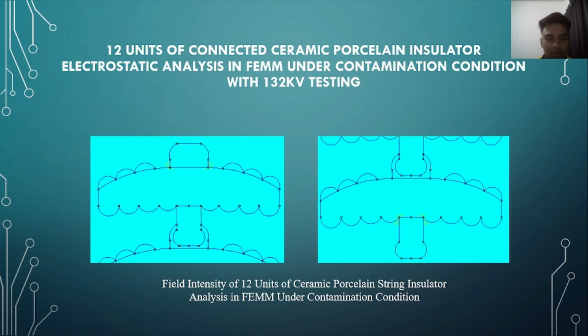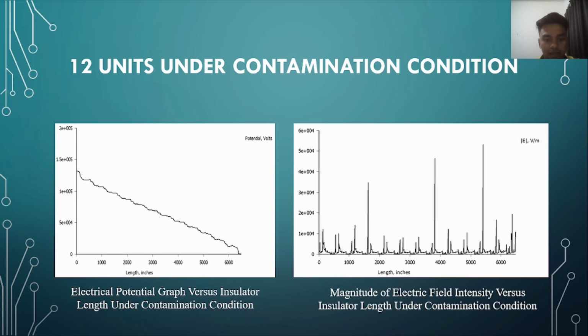Next we go to the first unit of the ceramic insulator electrostatic analysis in FEMM under contamination condition with 132 kV per phase. Here the field intensity is small, with a little field intensity above and under the insulator. This is the result for the contamination condition. In FEMM, the voltage is centered on the bottom of the insulator design, the voltage parameter was set to 132 kV, and the lowest voltage intensity was at the top of the first insulator design. The peak density of the unit of the insulator in FEMM under contamination condition is shown in this slide. Then the electrical potential graph and the graph of the magnitude of electric field intensity versus insulator length under contamination condition.